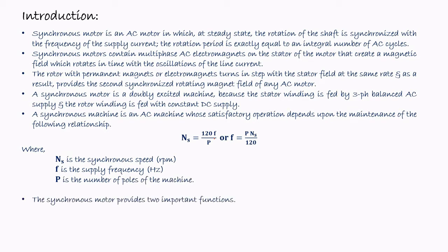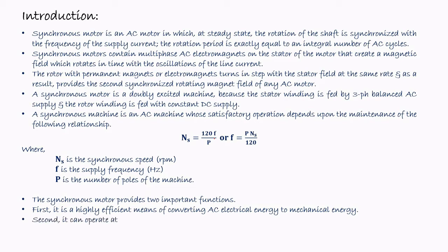The synchronous motor provides two important functions. The first is that it is a highly efficient means of converting AC electrical energy to mechanical energy. That is the basic purpose of a motor. And second, it can operate at a leading or unity power factor and therefore provides power factor correction. So the synchronous motor is a special type of motor which, at a particular condition, can draw electrical power at a leading power factor, or it may be at unity power factor.